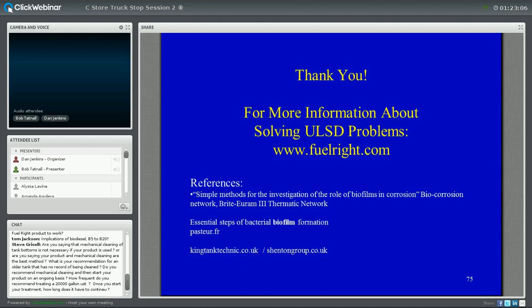We have a question on biodiesel B5 and B20. Right now we're testing B2 and B20. Good point. Biodiesel is a coming thing, and a lot of you may or may not realize that in states that don't mandate it yet, and most don't, it is still legal. The ASTM specification for number 2 diesel fuel allows up to 5% biodiesel blended in while still being in spec, so they don't have to tell the customer this contains biodiesel.